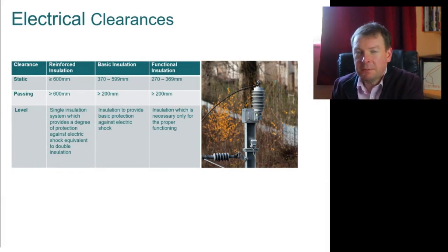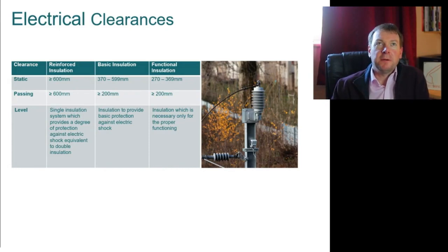What do we mean by electrical clearances? A lot of our conductors have to be exposed. Think about the electricity supply in your house - all of those cables are safely insulated, with a wire cover, so you can't touch the conductor. With overhead line, you can't do that. Because of the sliding contact mechanism, they have to be bare. So how do we insulate the live from the earth? Because you still have to do that to avoid short circuits.